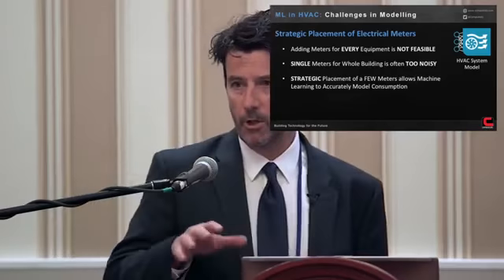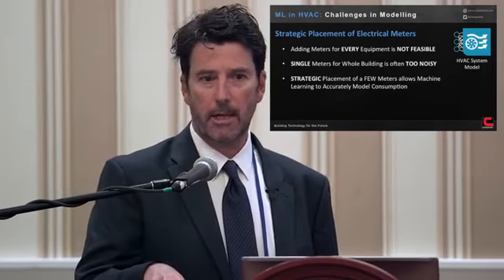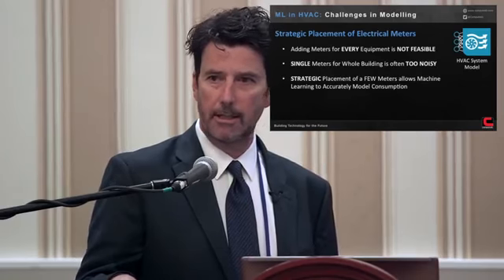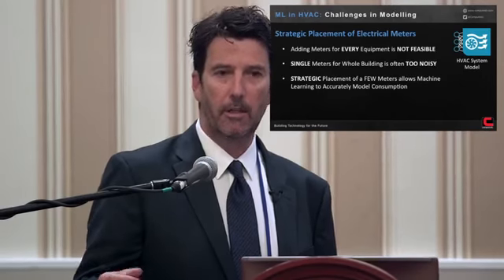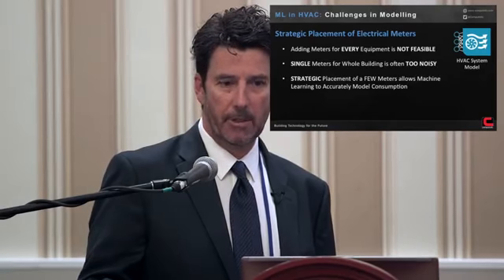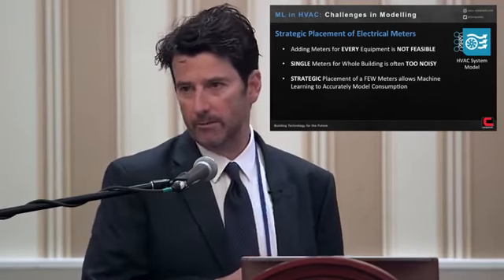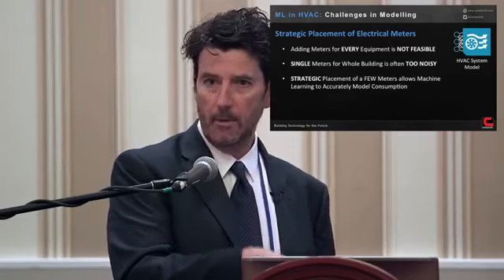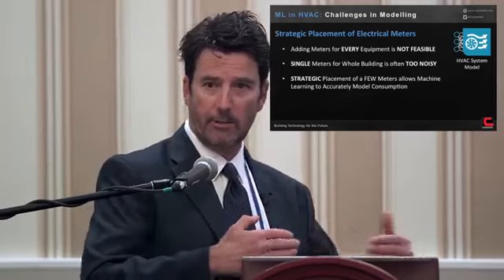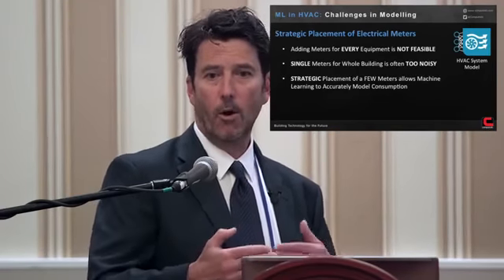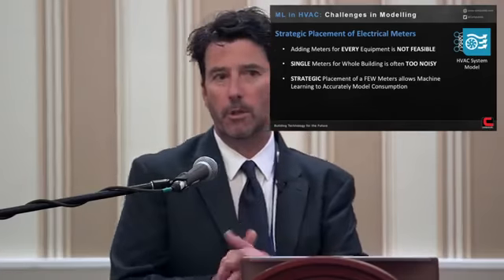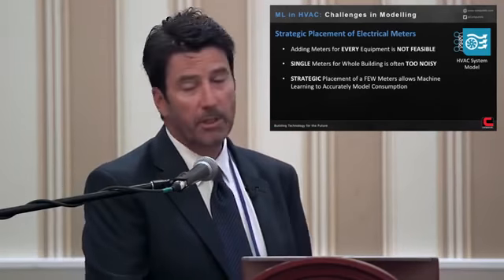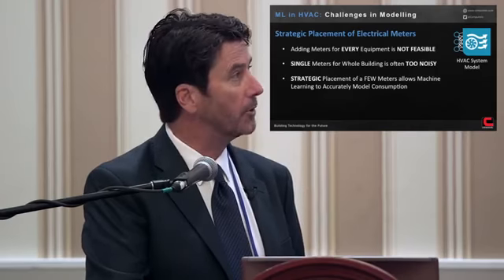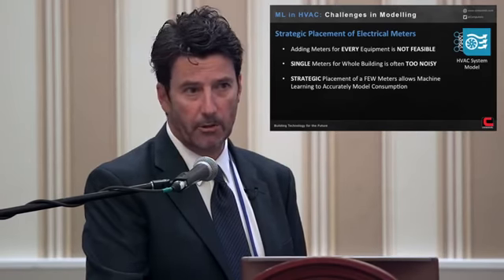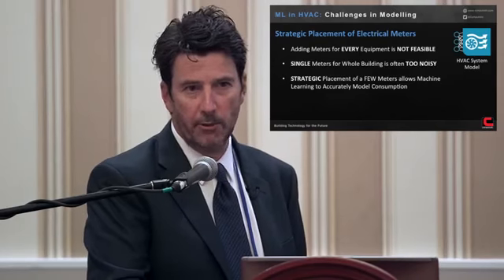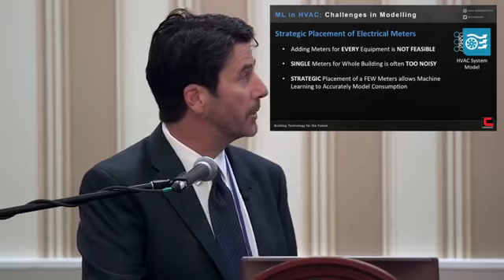What we try to do is go in, look at the electrical drawings, and strategically place meters in a way that helps us rapidly learn and understand the KW demand from each one. So if you had 15 pieces of equipment on one circuit, I'll drop a meter on that circuit, and over time watch as I turn those pieces of equipment on and off, I'll learn the individual contribution of each one to KW demand. Strategic placement of meters is something we've been spending a lot of time on recently. We go in, analyze a building's electrical system, and if you can afford to put in 10 meters, we'll tell you the best place to put them to get the most bang for the buck.